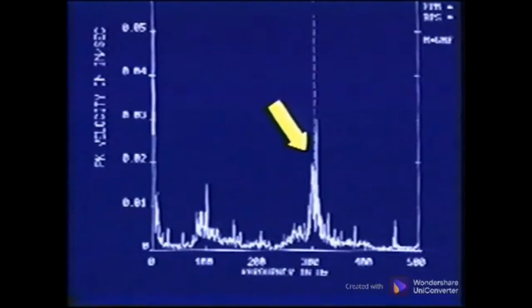The peak at 304 Hz is the gear mesh frequency, and the sidebands are spaced at 1 times turning speed of the shaft. The energy in the area of 100 Hz is the resonant frequency of the gear. This is a typical example of gear wear. When gears wear, the surfaces tend to strike as they mesh, exciting the natural frequency of the gear. The natural or resonant frequencies can be determined using an impact test.